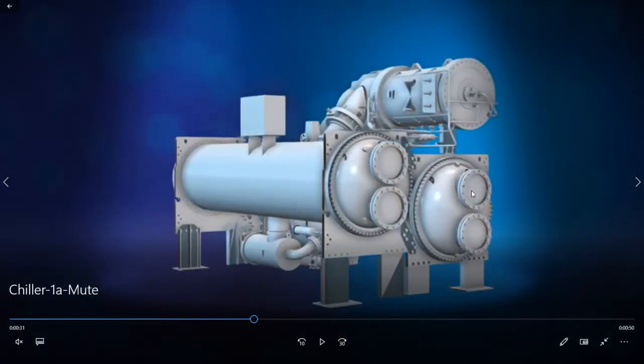Now these connections over here are for water. We have a water cooled condenser, so you will have the water coming into the condenser, and it will then be sent to the cooling tower. So there are two connections for the water, one inlet, the other the outlet.